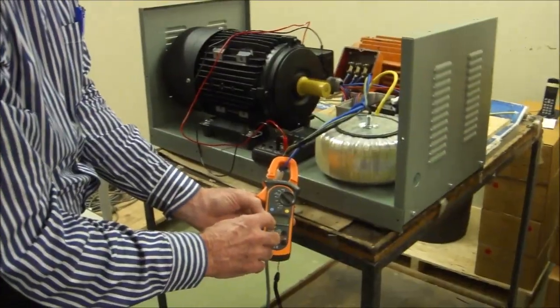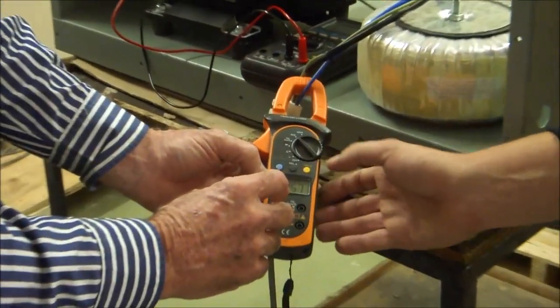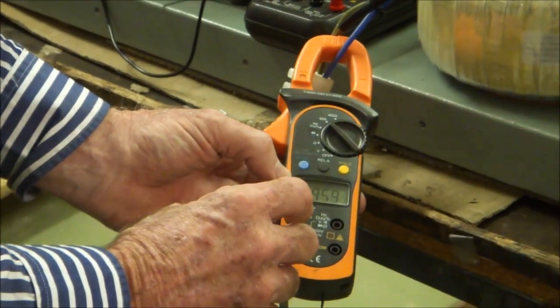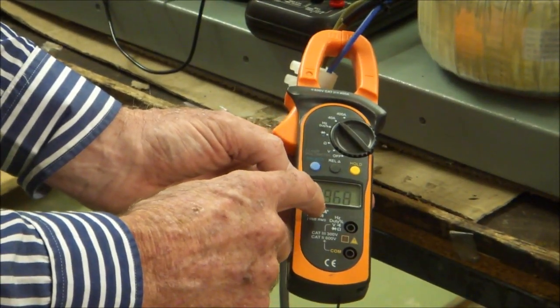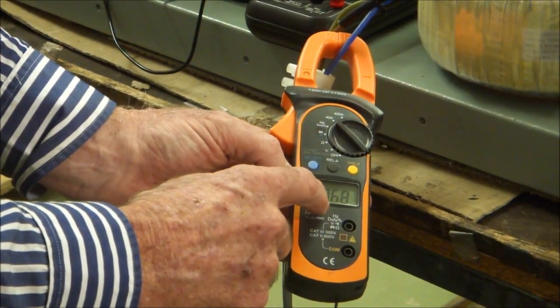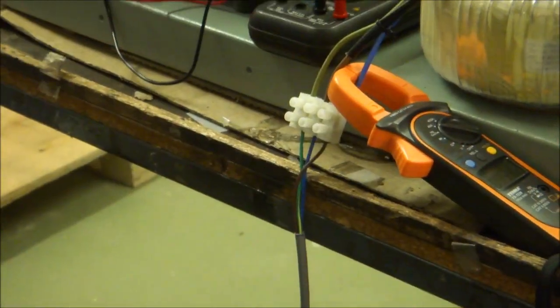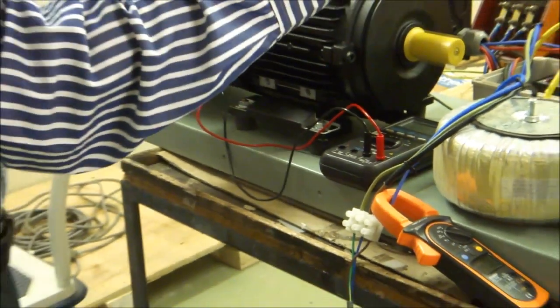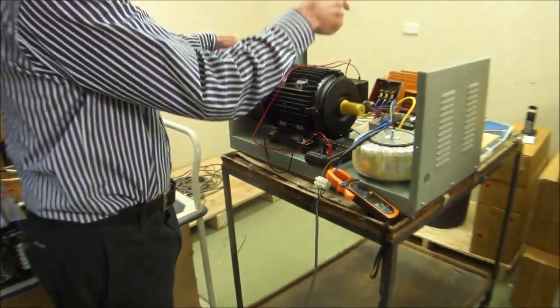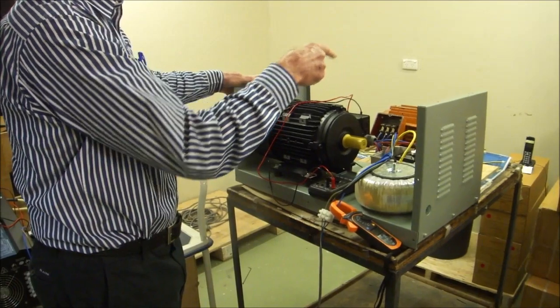The input current on the single-phase is 9.68 amps at 50 hertz. So now that we've got the single-phase to three-phase converter running, now we'll energize the load motor.